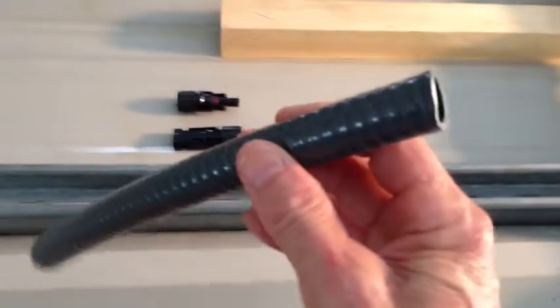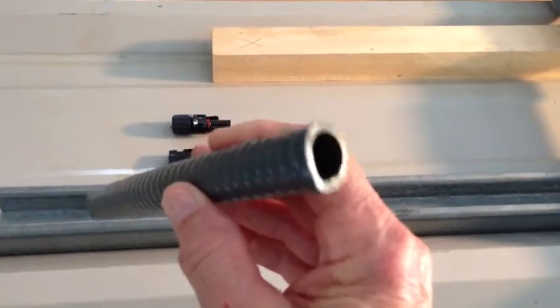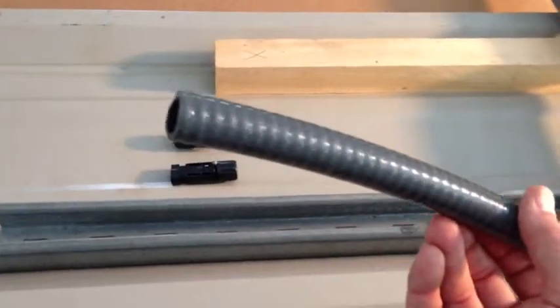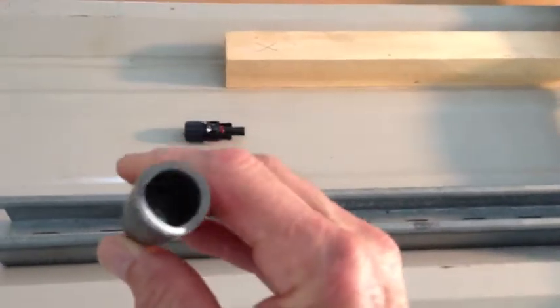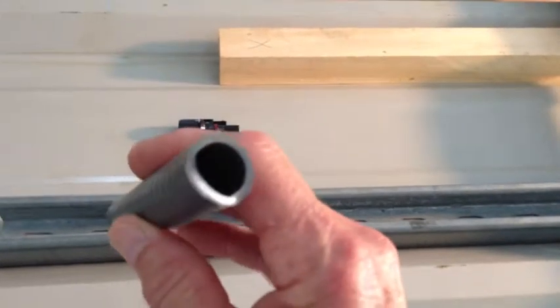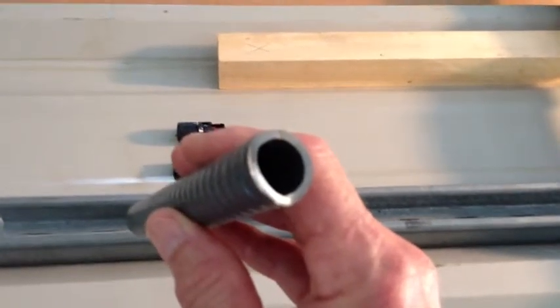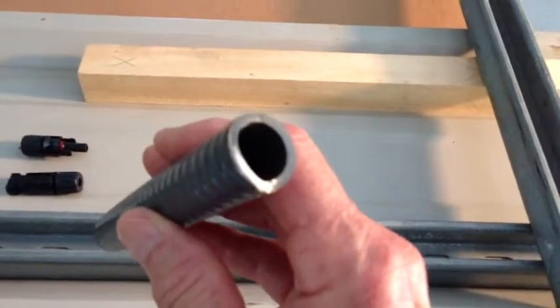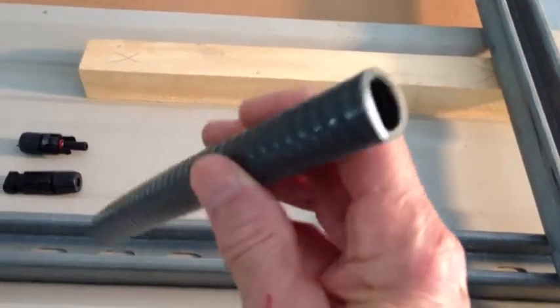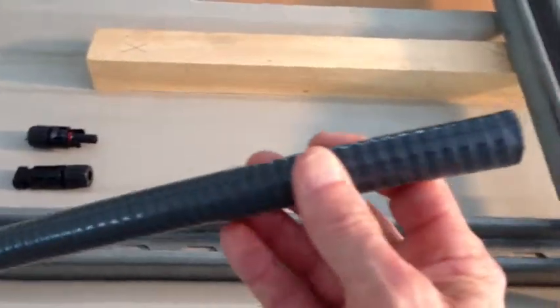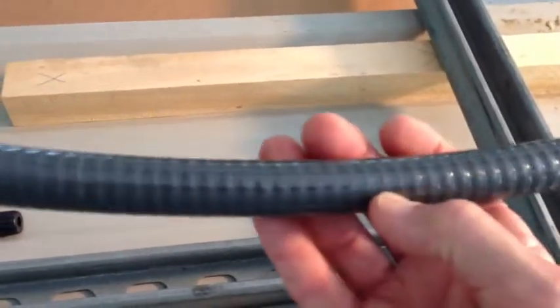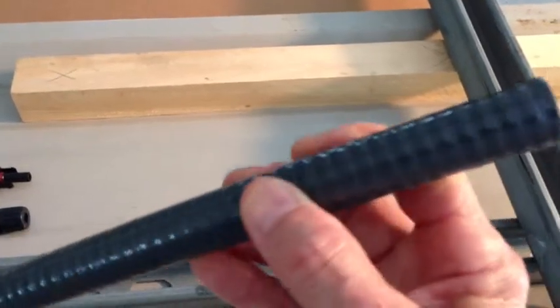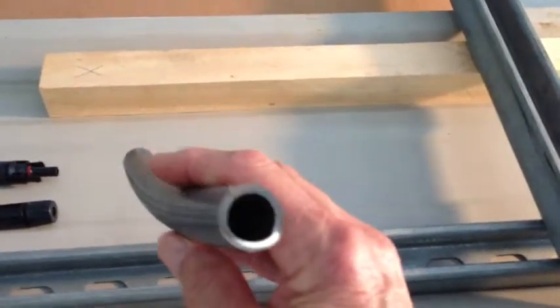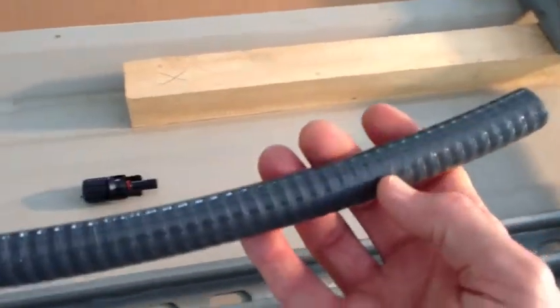Now, as far as the cabling is concerned, what I use is number 8 standard stranded cable, like you can buy at the big box places, not rated for any exterior use, and I ran them in flexible half-inch conduit. Now this flexible half-inch is a little tight when you're pulling a fairly 25 feet of number 8 cable through it, two strands. So you might want to wipe the cable down with a moist cloth or something, and it pulls through a lot easier. So when you run this up, this protects the cable, so you can use the THHN, I think is what it is. You can use that okay externally as long as you have this kind of protection on it.